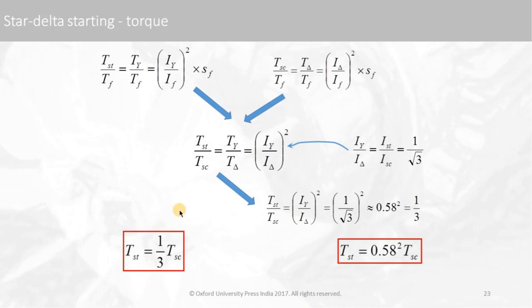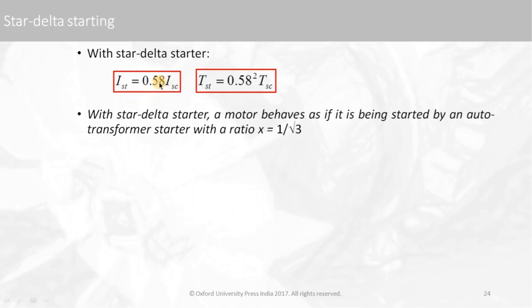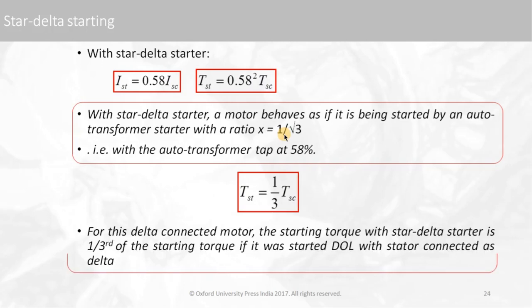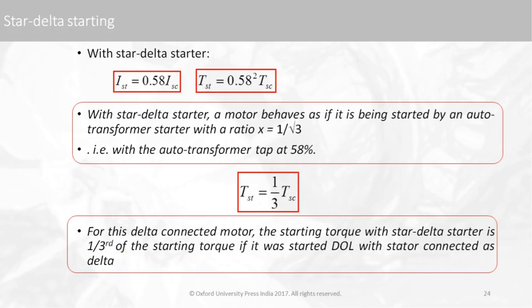This is all about the star-delta starter and auto transformer starter. The current is reduced to 0.58 of the short circuit current and the torque is one-third (0.58 squared). The star-delta starter behaves as if the motor is started by an auto transformer with a tapping ratio of 1/√3, which is about 58%. For a delta-connected motor, the starting torque with star-delta starting is one-third of the starting torque if started directly as delta. This concludes today's class on starting of squirrel cage induction motors. In the next class we will start speed control of three-phase induction motors.